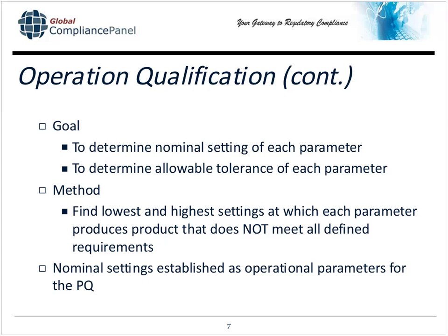You also want to determine the allowable tolerance of each parameter, because even though you set at 100 degrees, it could drift a little. So you want to make sure that when you set it at 100 and the temperature reads 101, 98, 103, for example, that you're within your tolerance, because not just the visible tolerances, but if you neglect to calibrate your temperature reader, for example, you want to make sure that you're within a reasonable tolerance.